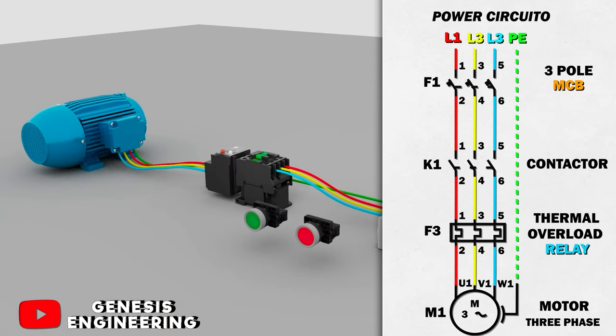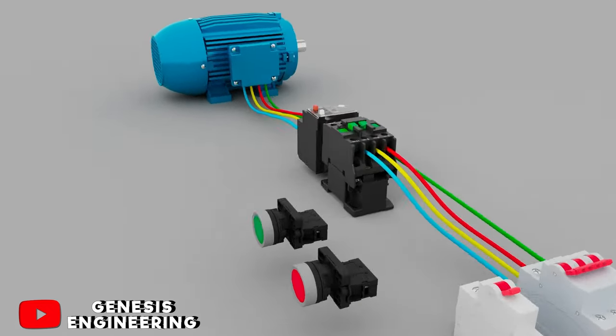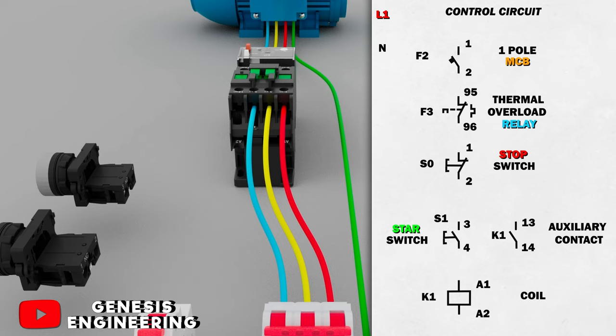Now let's make the command circuit. For each circuit it is necessary to have a miniature MCB circuit breaker. For the power circuit we put a three-pole MCB and for the control circuit we put a one-pole MCB. We start the command circuit by connecting the neutral conductor directly to A2 of the contactor.